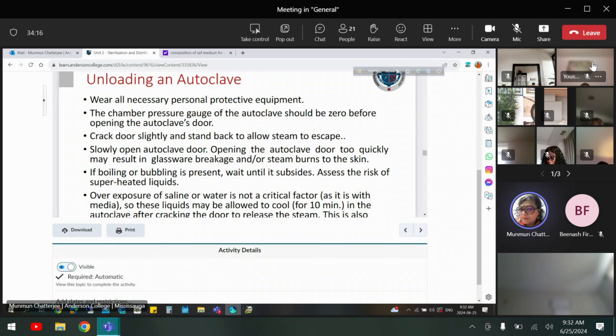Slowly open the autoclave door. Opening the autoclave door too quickly may result in glassware breakage because of the sudden temperature difference, and steam also burns the skin. If boiling or bubbling is still present, sometimes even if the pressure has come down to zero the inside temperature still holds. If you see any liquid bubbling, wait. When it settles down, then you are going to take it out.